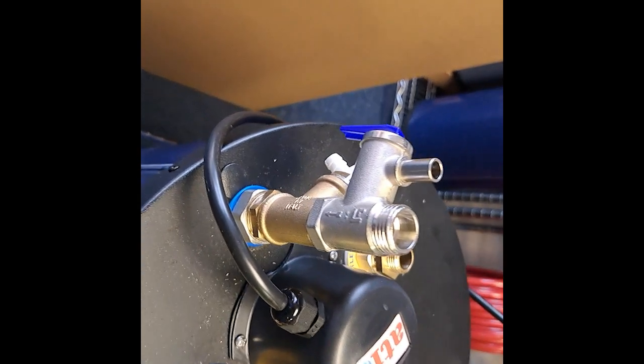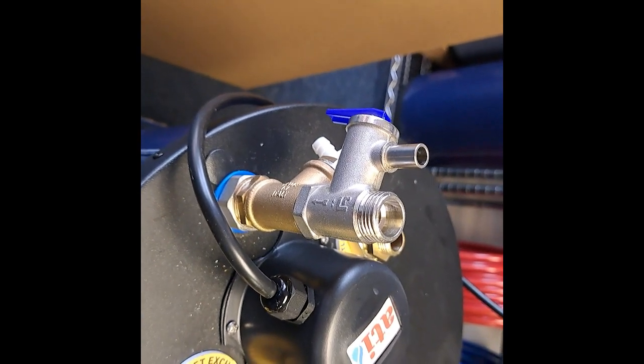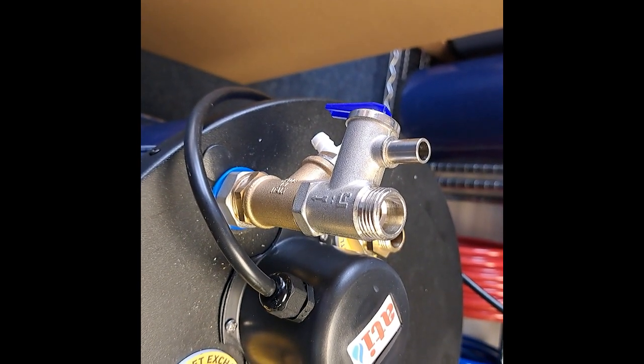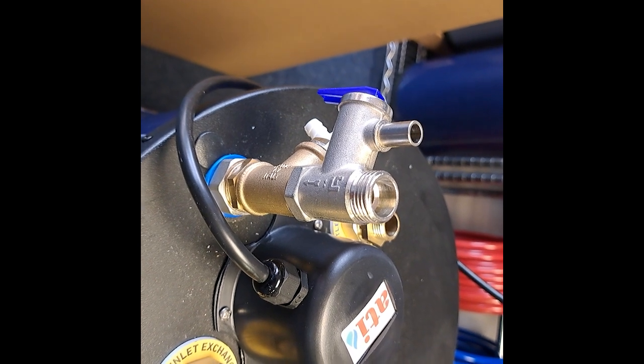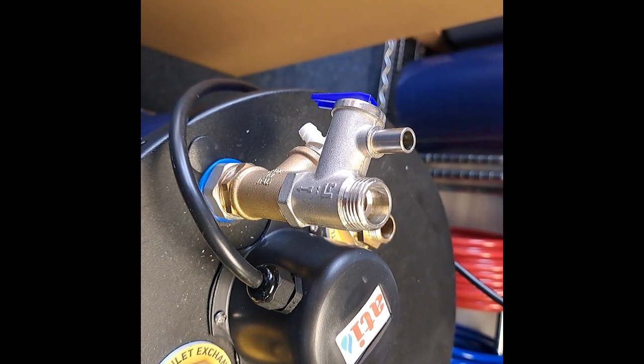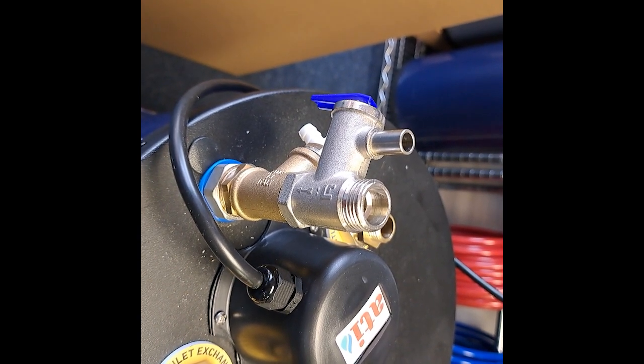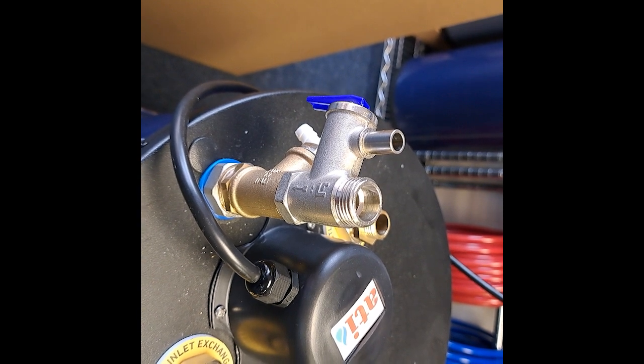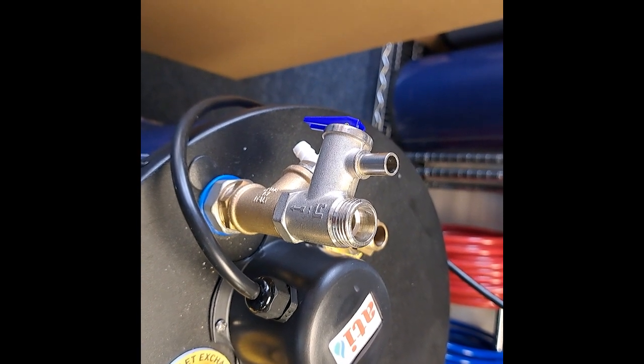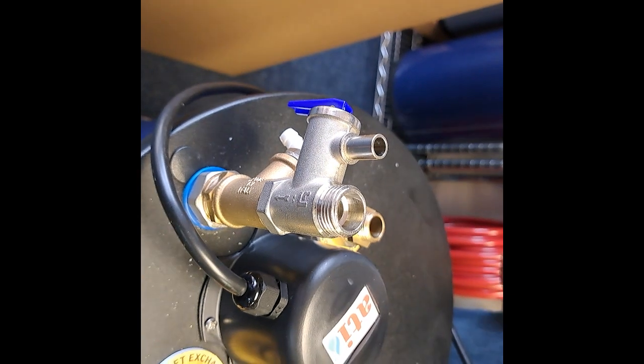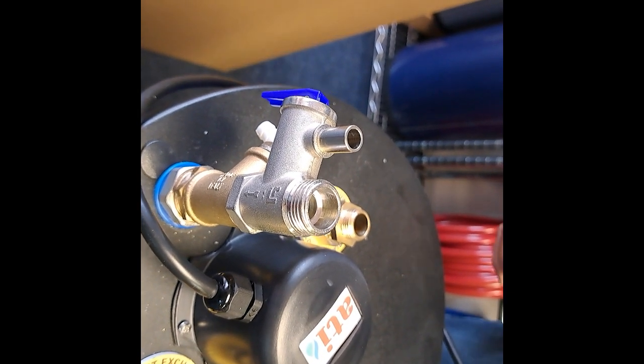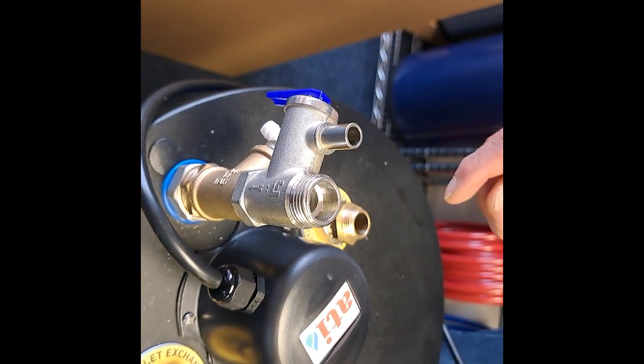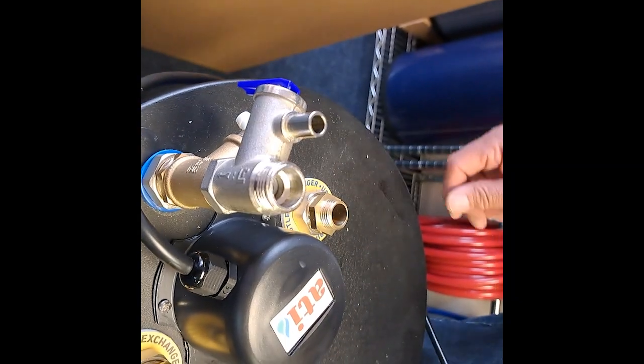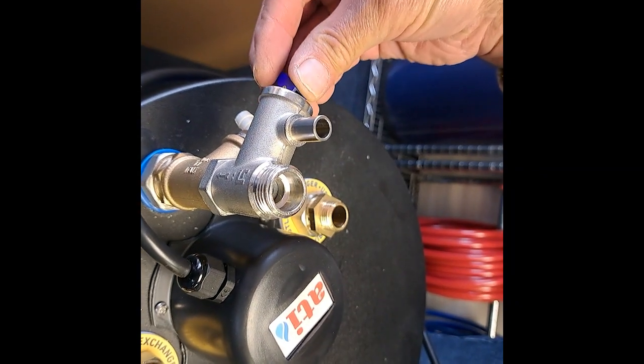Another component you may need to check from time to time is the pressure relief valve. Current ATI models have 8-bar valves indicated by a blue handle. Older models have a 6-bar valve with a black handle. If you notice any weeping from the relief valve, this may be down to some debris on the inside. To clear it, make sure the water isn't hot and then open the valve to drain some water out.